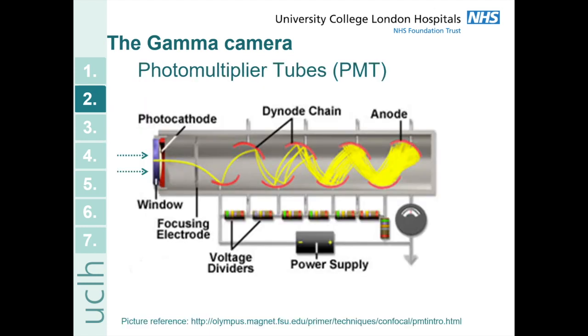The next stage of the detector is the photomultiplier tubes or PMT. Visible photons from the scintillator come into the PMT and produce an electrical signal — it converts visible light photons into an electrical signal. The visible photons hit the photocathode, which converts them into electrons. Those electrons are then accelerated through a voltage and come into contact with the dynode chain. Each time they hit the dynode the number of electrons is multiplied, magnifying the electrical signal, and it is this signal that is read by the electronics to create the image.